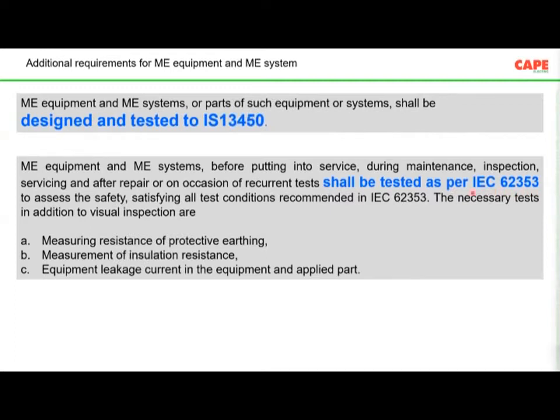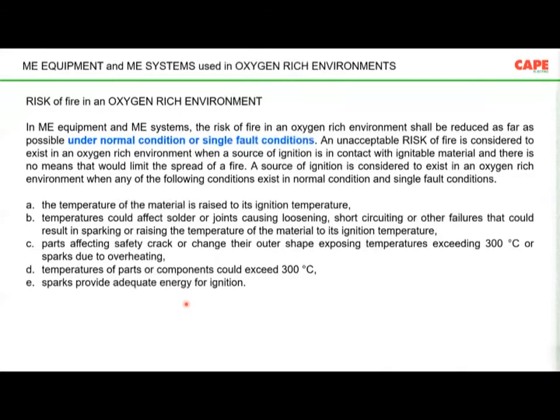So what does this particular standard say? You are supposed to test the resistance of protective earthing. That means from the equipotential bonding bar to your equipment, you have an earth wire. The resistance of that wire must be less than a certain limit, so you are supposed to measure it. Measuring insulation resistance is required. Then the equipment leakage current to the equipment and applied part. These three measurements are mandatory for every biomedical equipment or ME and ME system once you connect or reconnect it into your system.